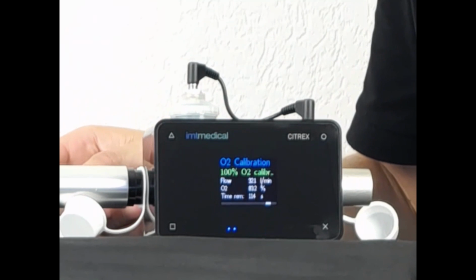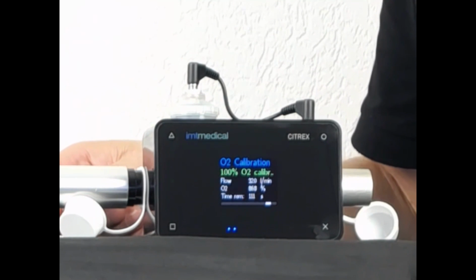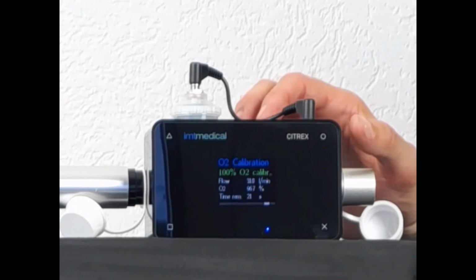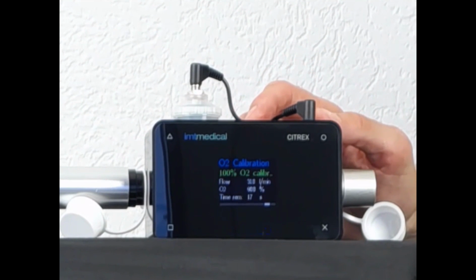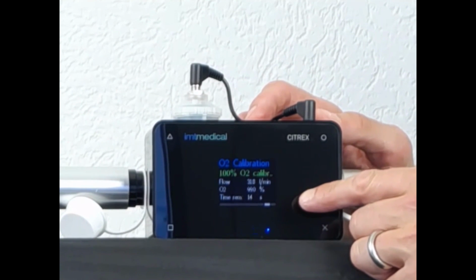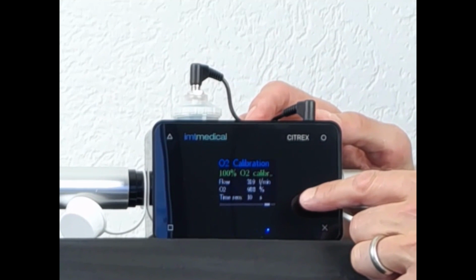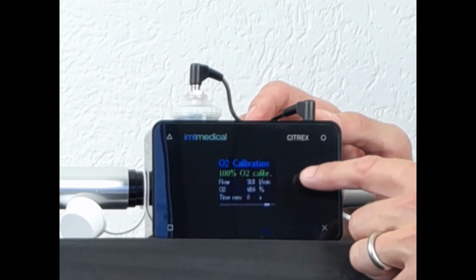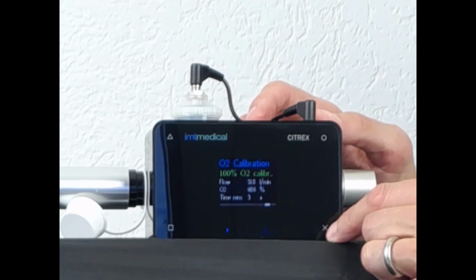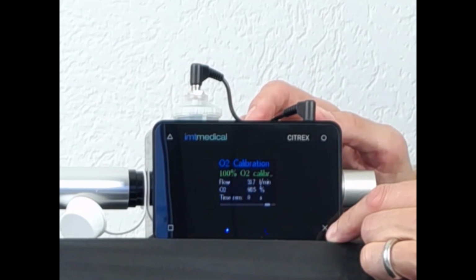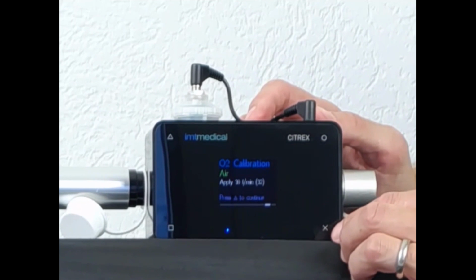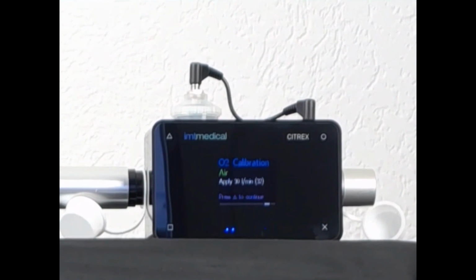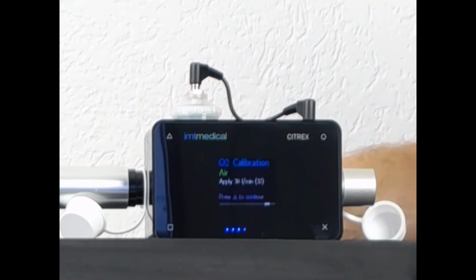It takes 2 minutes on 100% oxygen, and it takes 2 minutes on air. So we have now 15 seconds of 100% oxygen calibration left. After this, the device will prompt us for 30 liters of 21% air, which it is doing right now. I have to apply 30 liters per minute of air, which again I do from the service level of my ventilator. So now I have changed to air, 30 liters of air. I let the oxygen flow out a little bit, and then I start the calibration.